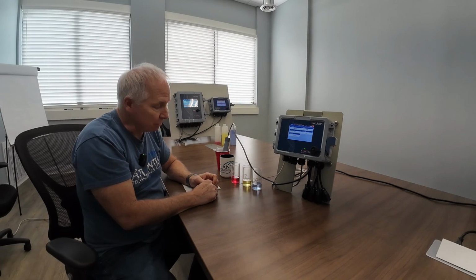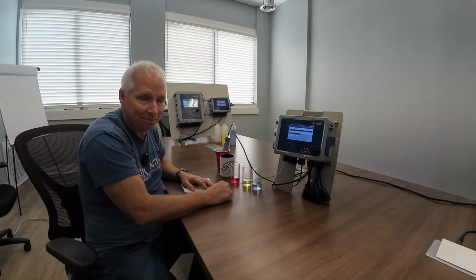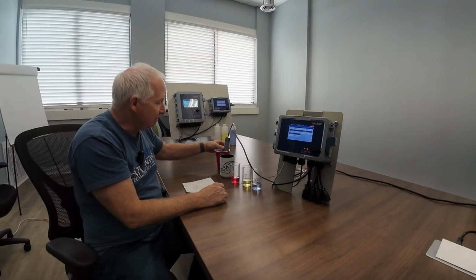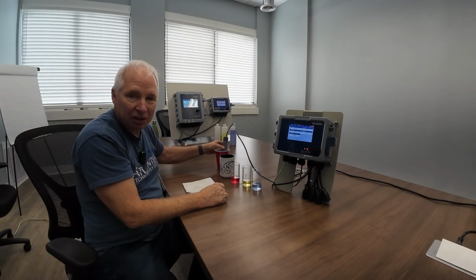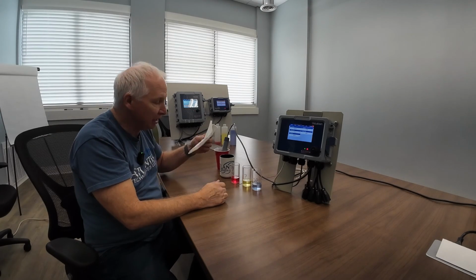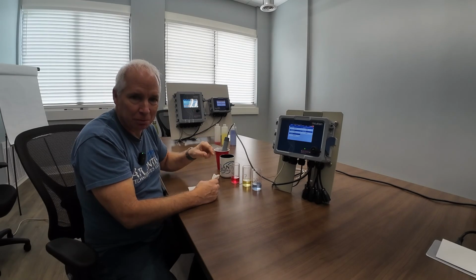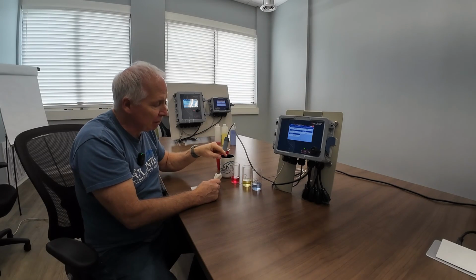I'm here today to show you how to do a 3-point pH calibration on a Walchem Intuition 6. What you're going to need today is your 3 buffers, which I'm using 4, 7, and 10. You'll also need some fresh water to clean the probe between the buffers, and a paper towel. It's that simple. As you're going through your buffers, make sure you never contaminate from one buffer to another.